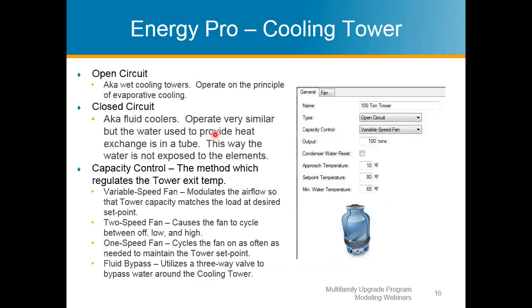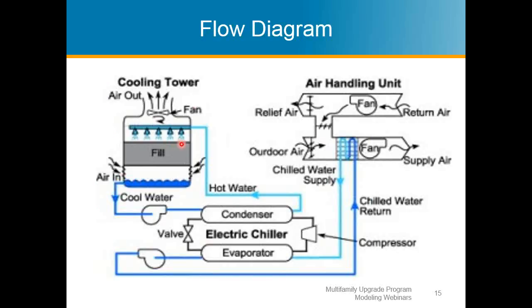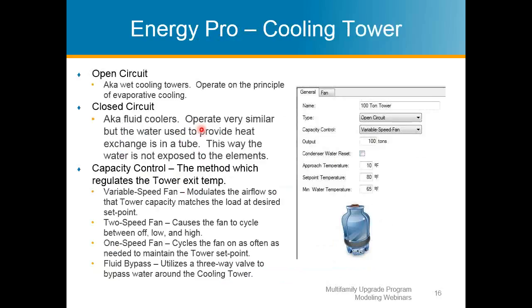So here's EnergyPro. Here's the cooling tower types. You can have an open circuit. So basically an open circuit is what I was explaining to you before, where the water is just free water that's coming out, being exposed to the elements. So that's called an open circuit. Now you can have a closed circuit, which is basically that water is now going through pipes, and it's not going to ever be met by the outside elements. It's still using the outside air to cool down on the cooling tower side. However, it's just not water that's raining down on the fill. It's a different scenario the way that it goes. So that's a closed circuit type of cooling tower.